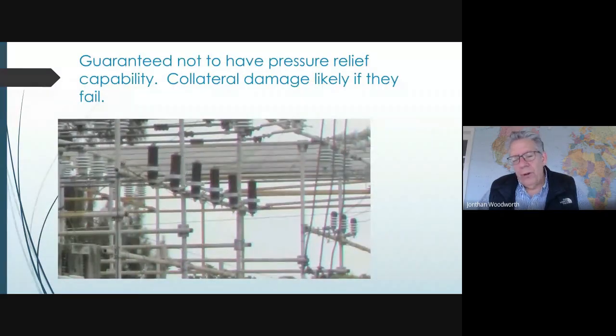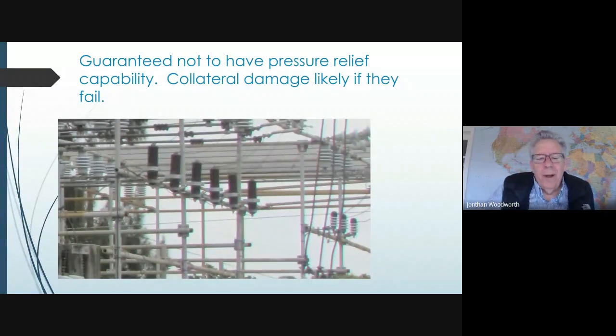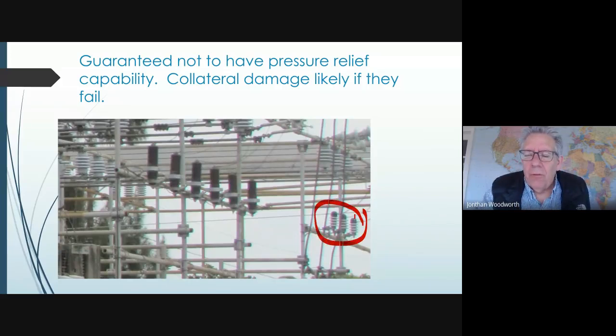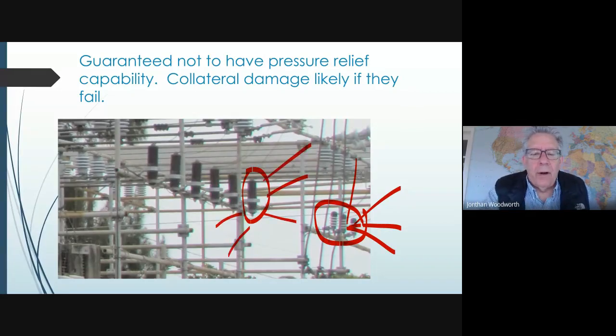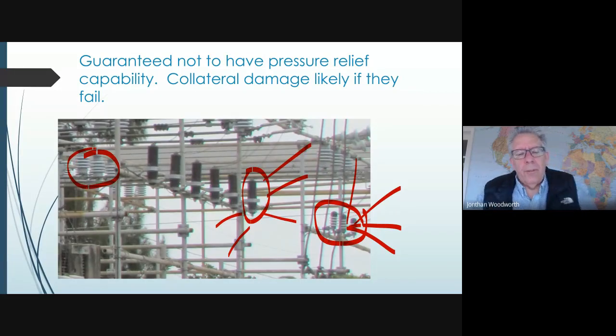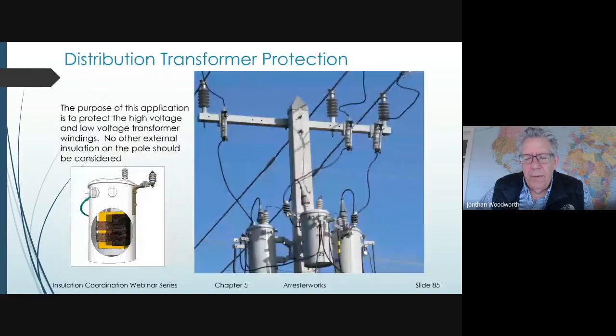Here's some old arrestors that are on that system. The reason for polymer arrestors is that they don't blow up. Porcelain arrestors, if they should fail, have a tendency of blowing up, and they can cause damage to other equipment that's higher in value. So the reason polymer housed arrestors have become so popular in the past 20 years is for safety.